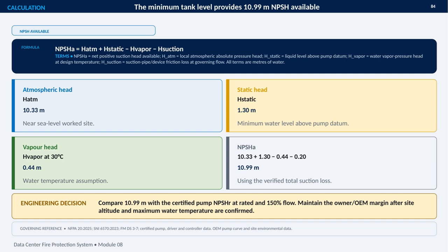Substituting those values gives 10.33 plus 1.30, minus 0.44, minus 0.20, for 10.99 meters of NPSH available. That result is not the final pump acceptance decision by itself. I need to compare 10.99 meters with the certified pump's NPSH required at both rated flow and 150% flow, while preserving the owner or OEM margin.